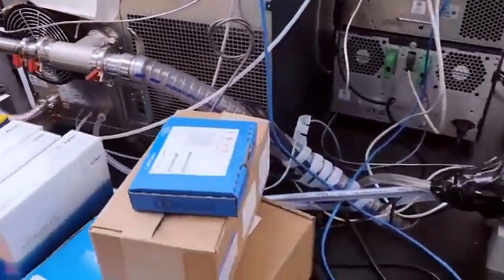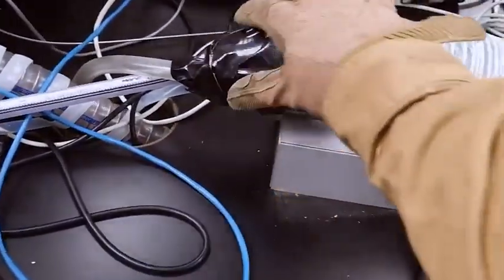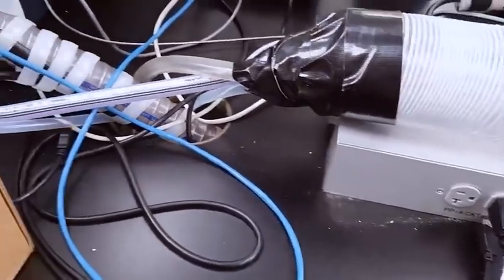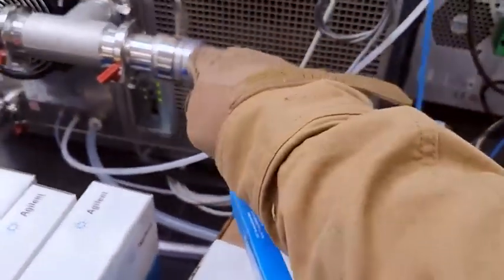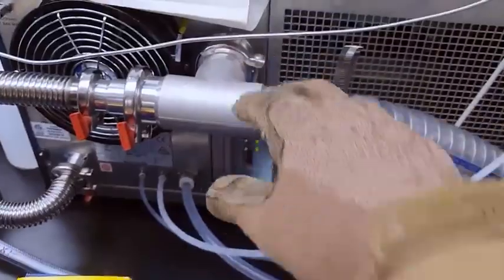Here's our handy dandy ventilation capture system — that's a MacGyver operation right there, but sometimes that's what you have to do. This is the rough pump vacuum hose for the back of the Waters mass spec. Look at all that heavy duty machining — that thing is really something. Let me show you the rough pump underneath the instrument right here.